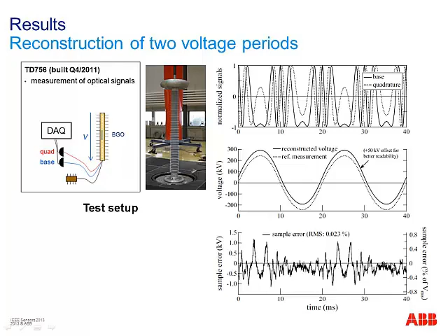More interestingly, of course, is what we get in average, because that's what you need in order to fulfill your standards. So there are two very important standards in practice. One is the metering standard, and one is the protection standard. The first one you use to bill the electricity to your customers, and the second one you use to switch off some electrical lines when you have a problem on them. And for metering, we need an accuracy of 0.2%, and for protection of 3%. And what we can see here is that both standards are met with our prototype and will be met also with the corresponding product.